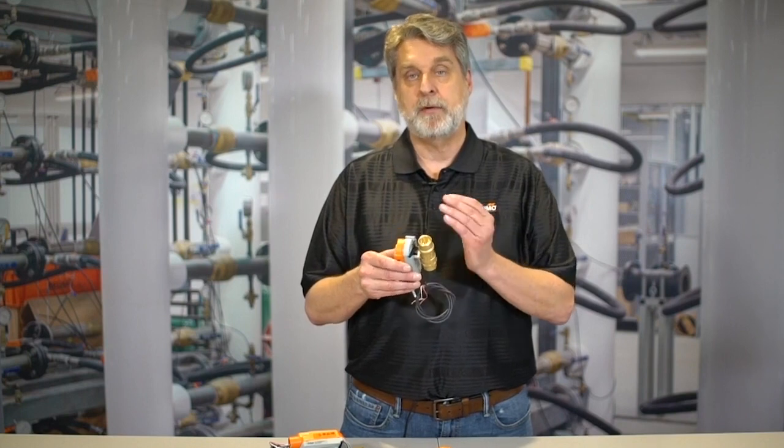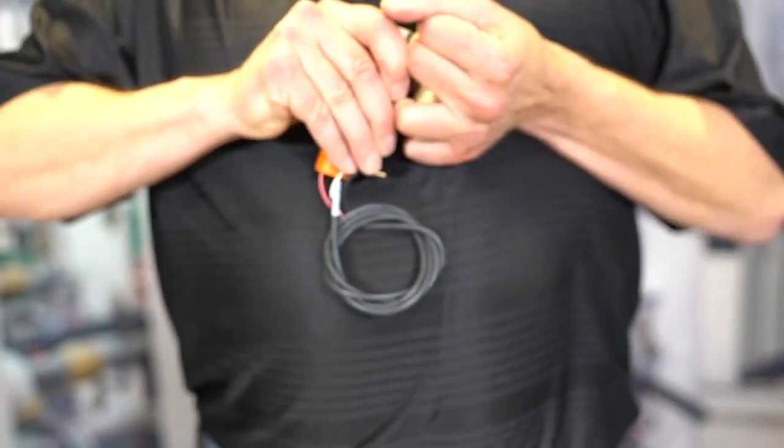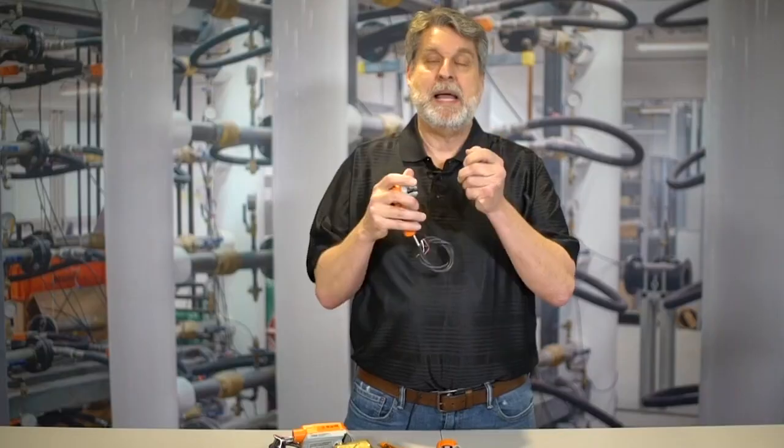First thing, very simple to take apart the zone valve. You don't need any tools, wrenches or screwdrivers, and you don't need to twist or turn. We don't want to break off the pins that are holding the valve to the actuator. I'm going to grab the valve body in one hand, grab the actuator in another, and pull straight up.